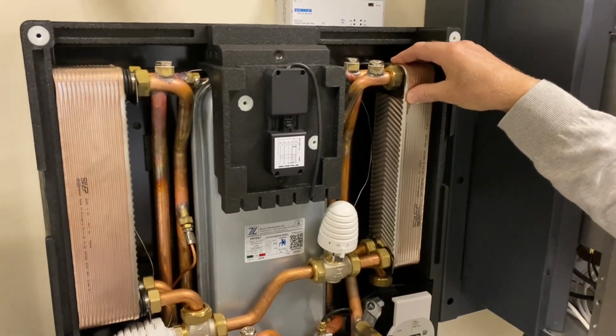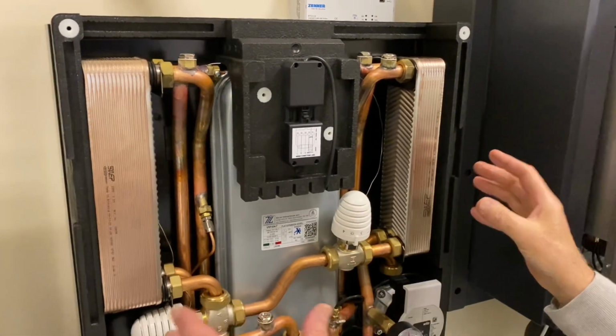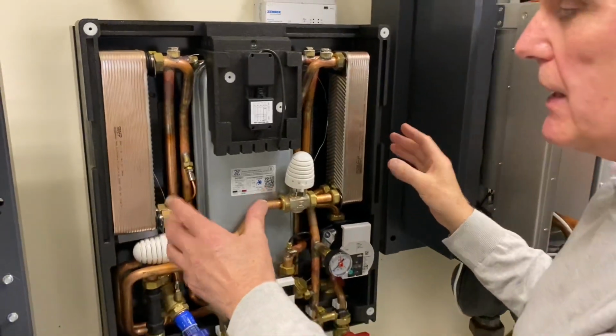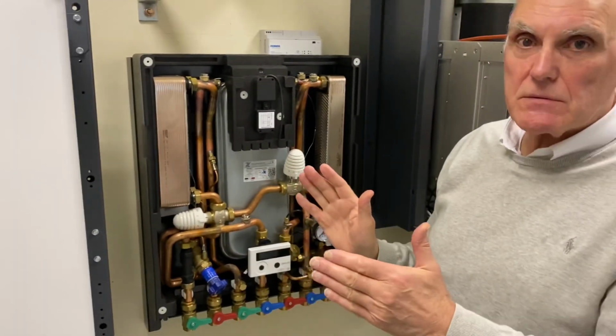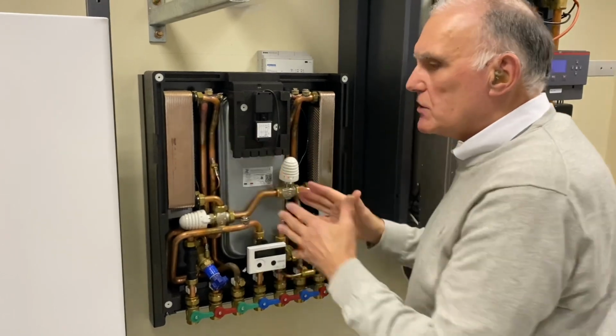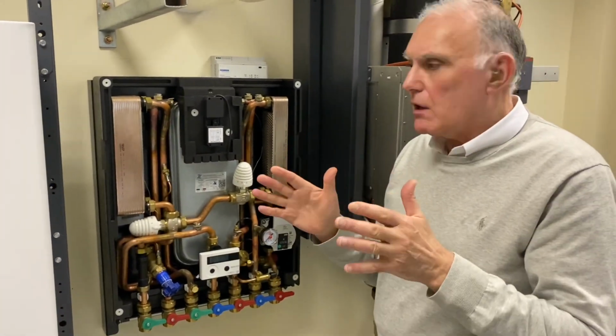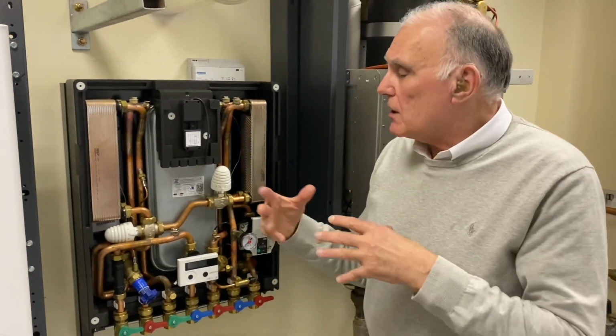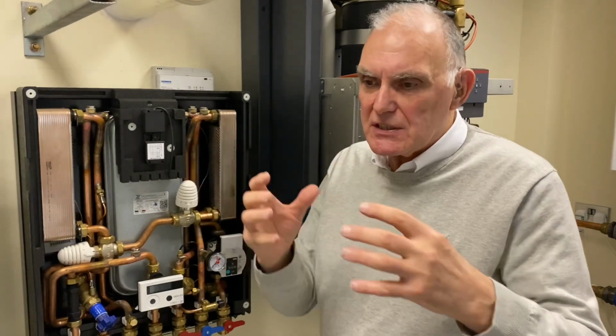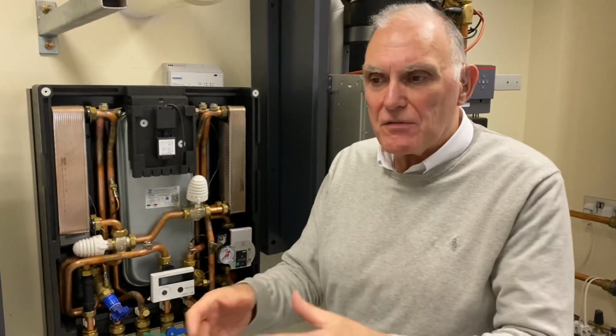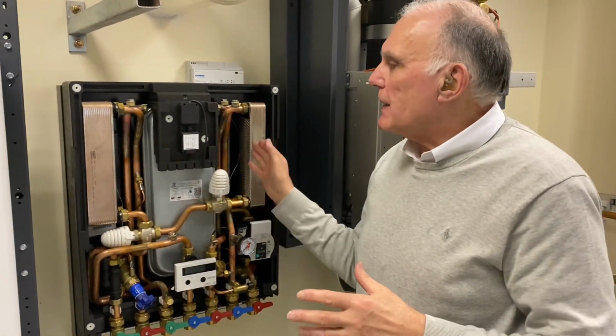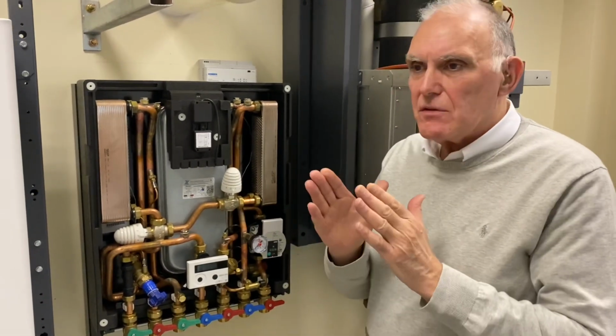One side goes over to the domestic hot water plate heat exchanger, and the other to the space heating heat exchanger. Now we must remember, the primary flow from the main plant is active at all times. So these plate heat exchangers are up to temperature at all times. So there's no lag, as in the combination unit. When you open a hot tap, you fire the main heat exchanger and have to wait a while for it to transfer its heat to the plate heat exchanger before you get any at the tap. These plate heat exchangers are hot all the time, so there's no delay.